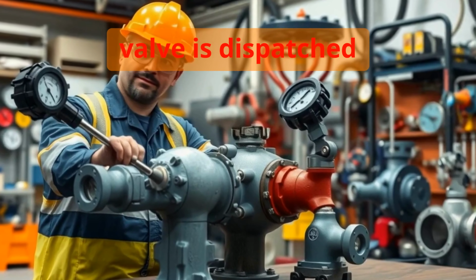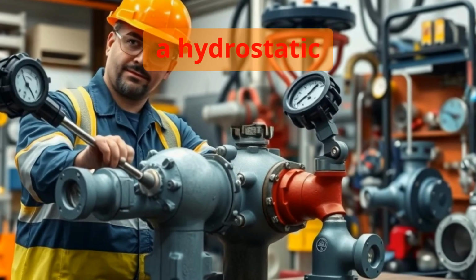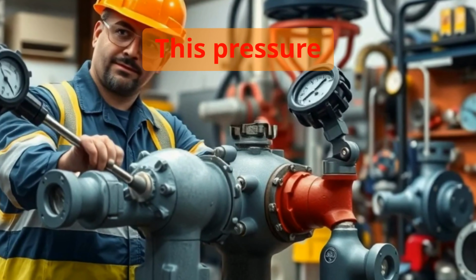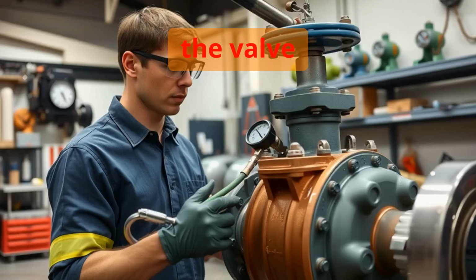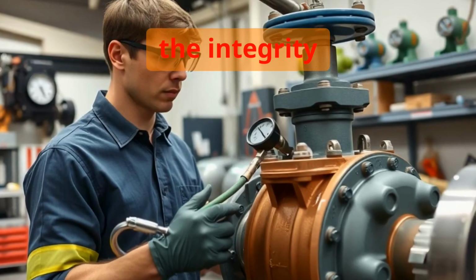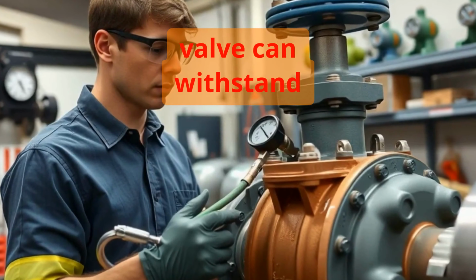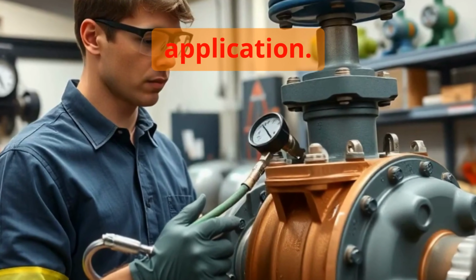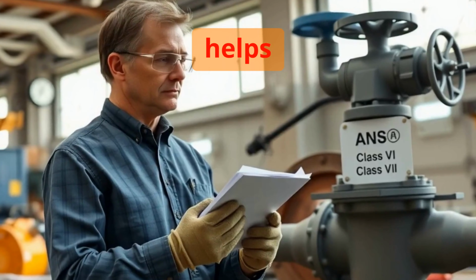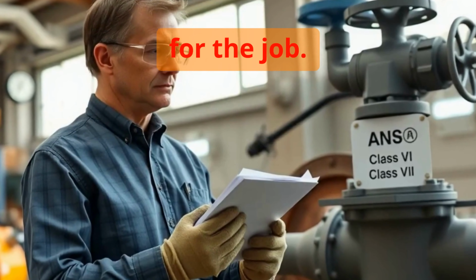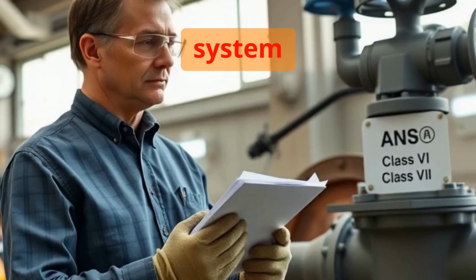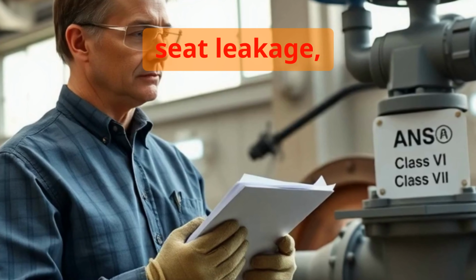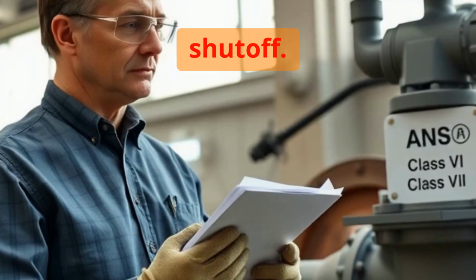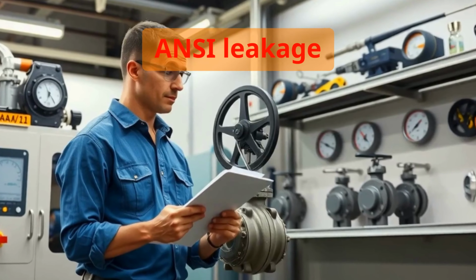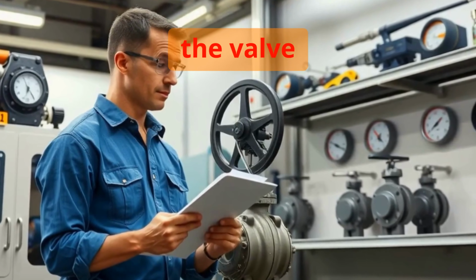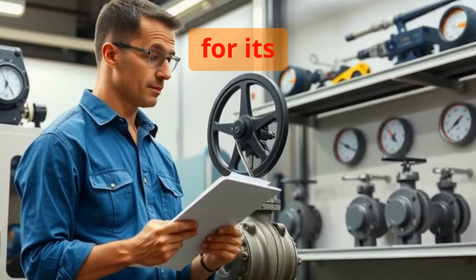Before any valve is dispatched for service, it must pass a hydrostatic shell test. This pressure test checks for leakage through the valve body, verifying the integrity of the shell and ensuring the valve can withstand the demands of its intended application. Understanding the ANSI leakage class helps engineers select the right valve for the job. This classification system defines allowable seat leakage, with Class 6 representing the tightest shutoff. Testing to a specific ANSI leakage class ensures the valve meets the required performance criteria for its application.